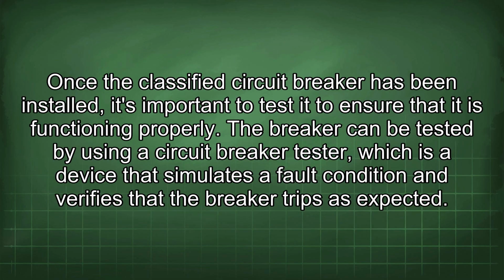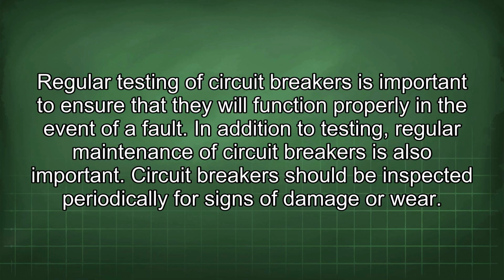Once the classified circuit breaker has been installed, it's important to test it to ensure that it is functioning properly. The breaker can be tested by using a circuit breaker tester, which is a device that simulates a fault condition and verifies that the breaker trips as expected. Regular testing of circuit breakers is important to ensure that they will function properly in the event of a fault.